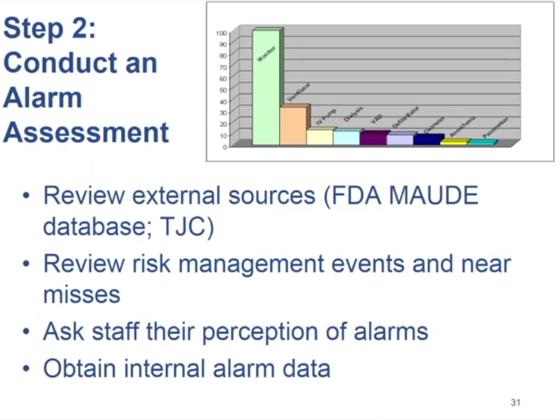You may want to also look at your internal risk management data to see if any medical devices have been linked to missed alarms or near misses, or talk to staff and obtain their perception of alarm fatigue. Most staff aren't even aware of the problem because they've just grown accustomed to the noise. It just becomes white noise. If possible, obtain objective data from your biomed or your IT department on the quantity of alarms. Now, the next few slides show how we measure alarms at Johns Hopkins Hospital.